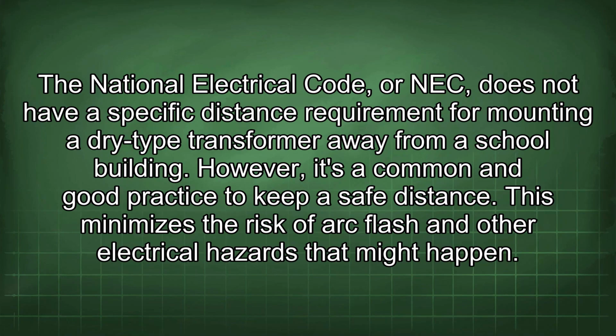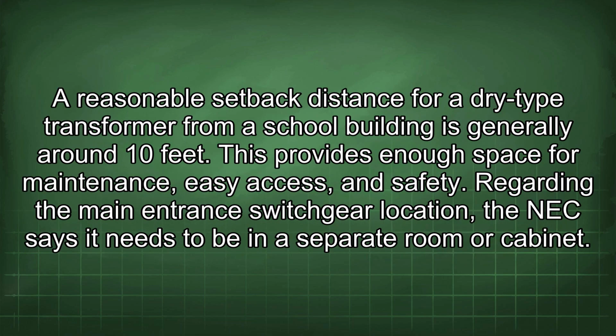The National Electrical Code, or NEC, does not have a specific distance requirement for mounting a dry-type transformer away from a school building. However, it's a common and good practice to keep a safe distance. This minimizes the risk of arc flash and other electrical hazards that might happen. A reasonable setback distance for a dry-type transformer from a school building is generally around 10 feet. This provides enough space for maintenance, easy access, and safety.